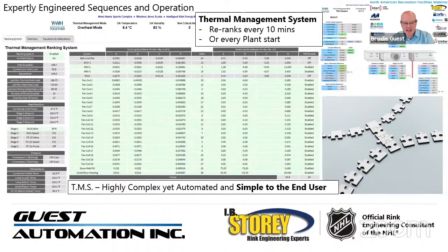Furthermore, it also knows when the next availability of energy will come and will hold off operating equipment that is purchasing more energy. Why heat a low occupied area when it's half a degree below set point? Areas like this can afford to drift slightly from set point to heat primary and prioritized areas. The longer a zone is below set point, it will simply get moved up the rank. The zone priorities are constantly changing as the TMS re-ranks automatically.